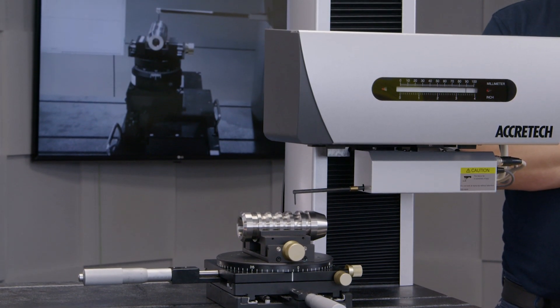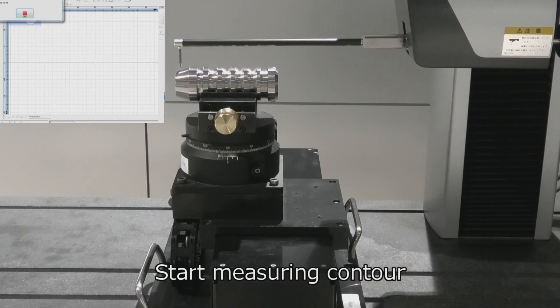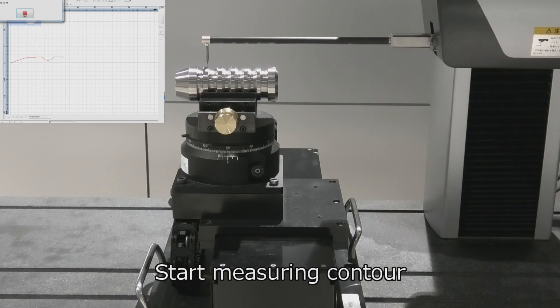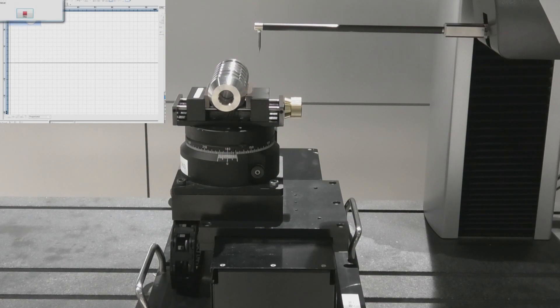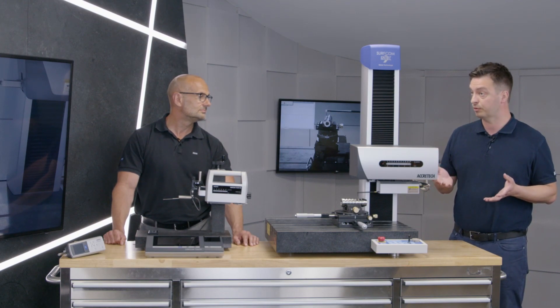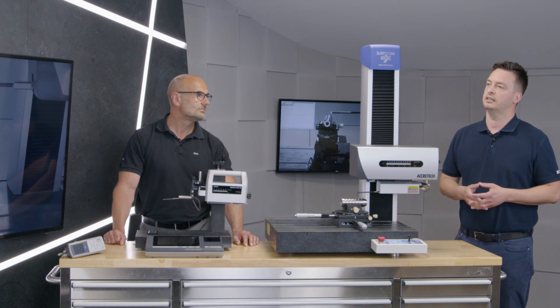The jump from manual measurement with the Surfcom Touch to the Next platform really is in CNC capability. The Next platform gives us full CNC capability across all axes — the column axis, the tracing driver or X-axis, and also the direction of stylus travel which is the Z-axis. This is a real world first — patented and designed by Accretech. We have linear drive technology inside the tracing driver, which gives us unparalleled straightness accuracy. The traditional method would be a ball screw, but the downsides of a ball screw are increased vibration, wear, and maintenance, so having linear technology really gives Accretech the edge.